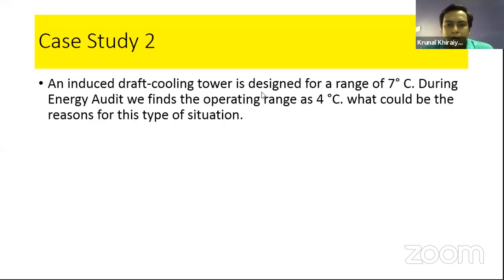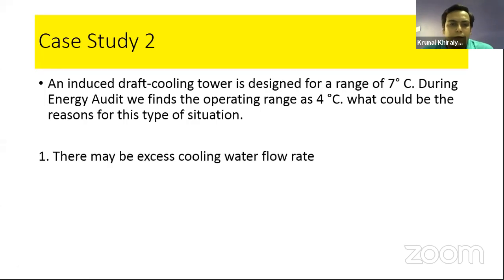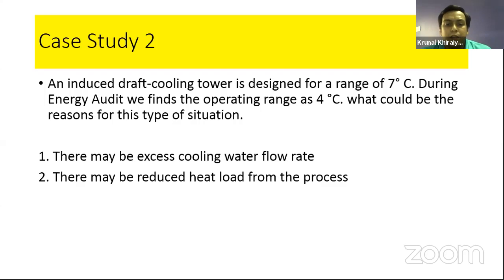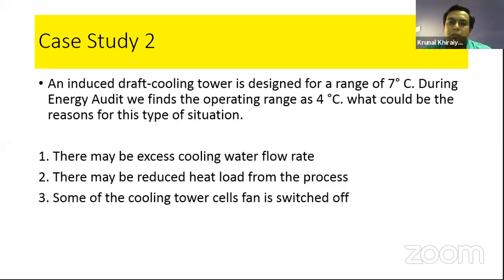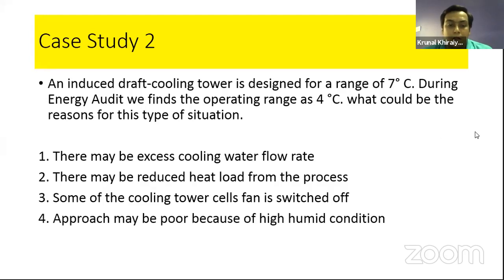An induced draft cooling tower is designed for a range of 7 degrees. During the energy audit, we find the operating range is 4 degrees. What could be the reason for this type of situation? Later on, we'll discuss one by one. There may be excess cooling water. If your water circulation is happening at a very high rate, you have a smaller range. There may be reduced heat load from the process, which means your heat supply or the cooling tower duty is also less. Some of the cooling tower cell fans may be switched off. Approach may be poor because of high humid conditions, and the nozzle may be choked. So these are the possible reasons when you get a smaller range.